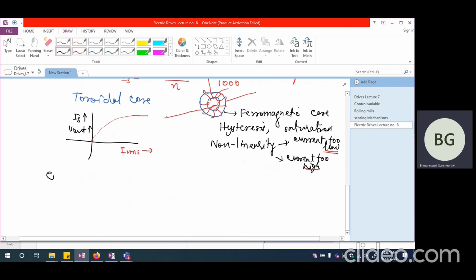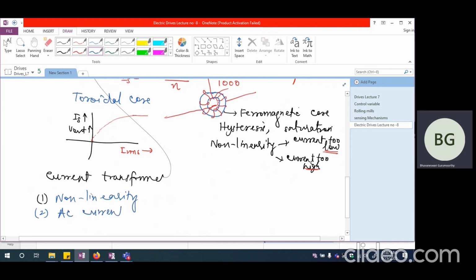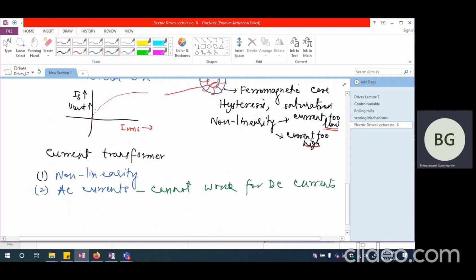Another thing is, one problem could be non-linearity. And another problem that can crop up is that it can work only for AC currents. It cannot work for DC currents, because a transformer will work only for AC current. So you are definitely going to see that it is useless in the case of DC current. It can work only for AC. And the third thing is, if you look at the turns ratio, we already said that I secondary divided by I primary, or I RMS, is going to be 1 divided by N.